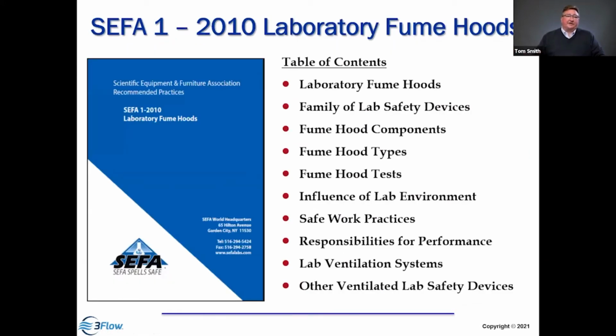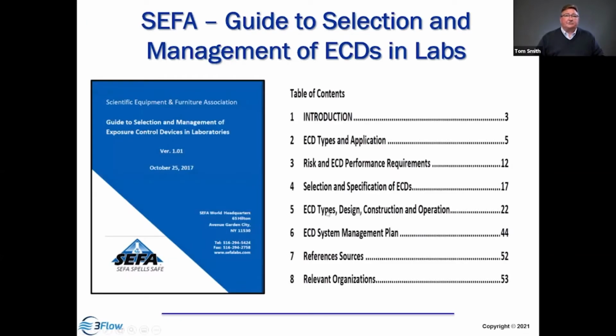I mentioned the SEFA document. The SEFA document helps to define the types of laboratory fume hoods. There's many different types and sizes. So this SEFA document, published by the manufacturers, talks about the different components, the types of testing, the influence of the environment, and some recommended work practices to make sure that hoods function properly. They've also expanded into the other types of exposure control devices. So it's not just fume hoods, but you may have biosafety cabinets or local exhaust snorkel hoods. You may have canopies and other types of devices that are used in the space that require ventilation.